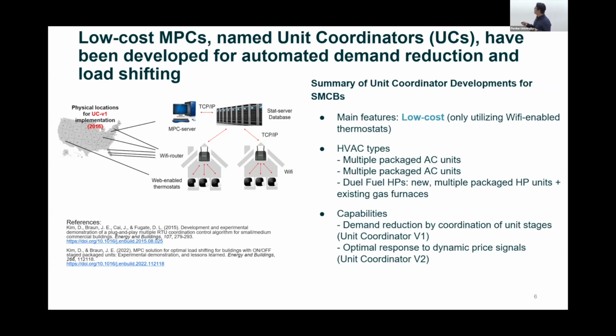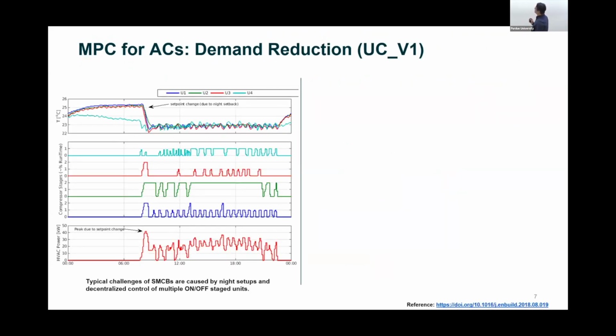And a capability of this model predictive control, we name it the unit coordinator because we are targeting the coordination of multiple rooftop units. Version 1 only tries to manage their peak demand by coordinating the operation of multiple units. But version 2 actually receives the grid signals and does some load shifting and load shedding accordingly. Some of the examples for version 1: the target is, again, only the peak reduction. And the left-hand side shows the temperature behavior.